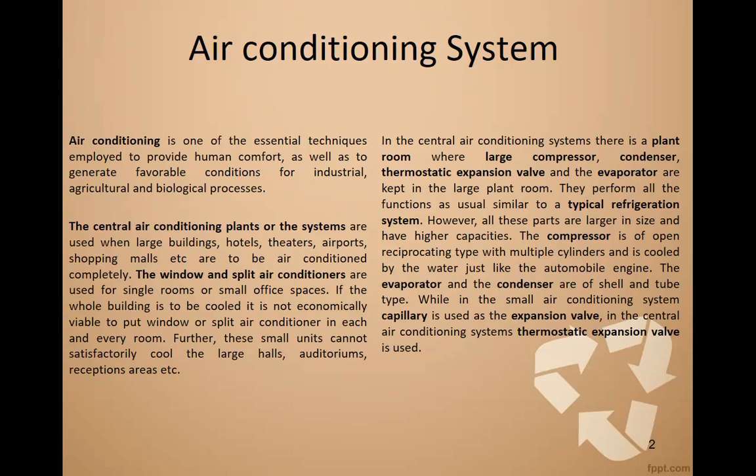The compressor is of the open reciprocating type with multiple cylinders and is cooled by water, just like an automobile engine. The evaporator and the condenser are of the shell and tube type, while in the small air conditioning system, a capillary is used as the expansion valve. In the central air conditioning system, a thermostatic expansion valve is used.